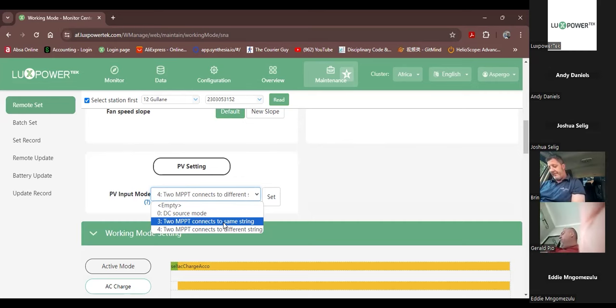It'll obviously go through an SPD, through a circuit breaker and some fuses. And then you can bring out two positives from the breaker and take it to the inverter. You can put one positive into PV1, one positive into PV2. You only need to bring one negative in because the negatives are common inside the machine. Or you can bridge the positives inside the machine with a suitable bonding jumper. And then you tell the machine that you've got two MPPTs connected to the same string. Then it knows that it's a much higher current coming in, and the power is shared across the two inputs.